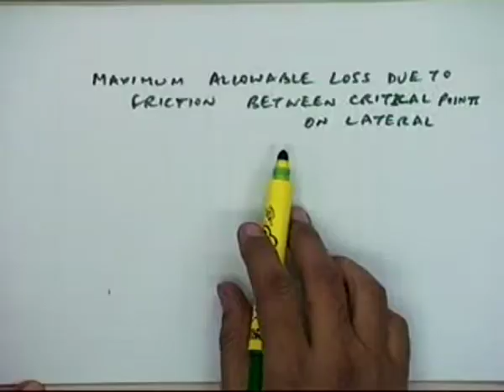In that case, some other sprinkler position can be critical, because the differences made by the elevation difference will make the major change in the overall pressure available at that particular location, and that can be much higher than at the sprinkler which is even farther away. So from the design purpose, that in-between sprinkler can also be a critical sprinkler, because you are designing for the extremes. Whichever is the extreme case, you will first have to select which sprinkler head is creating the maximum difference. That has to be picked up.